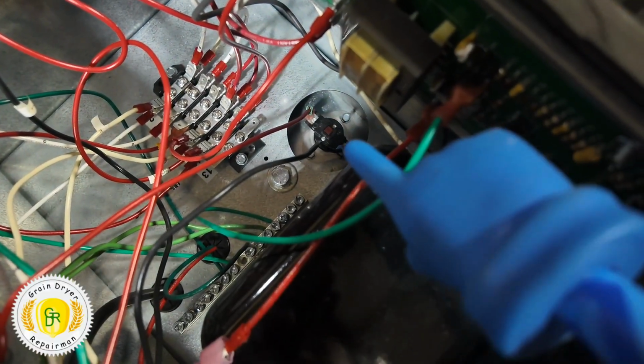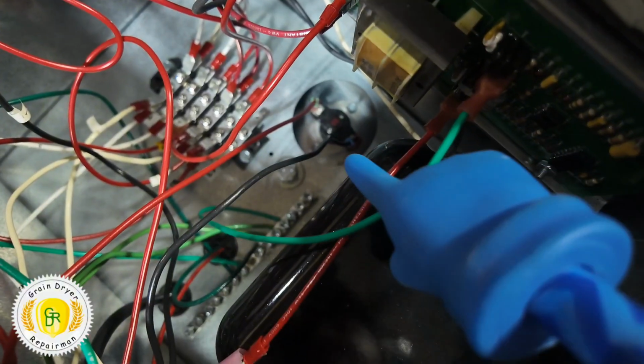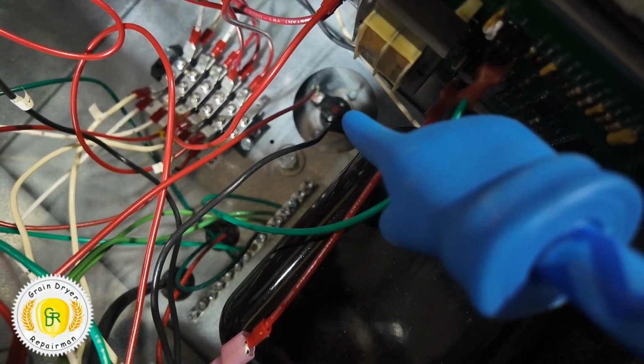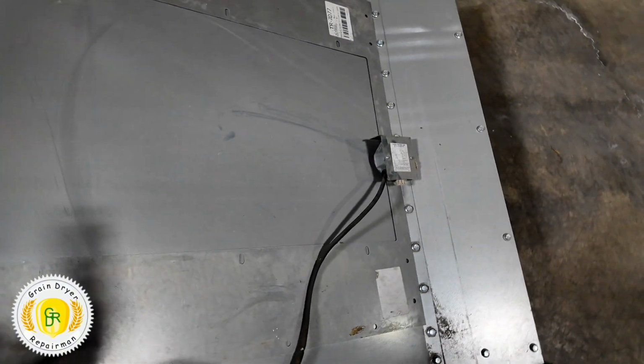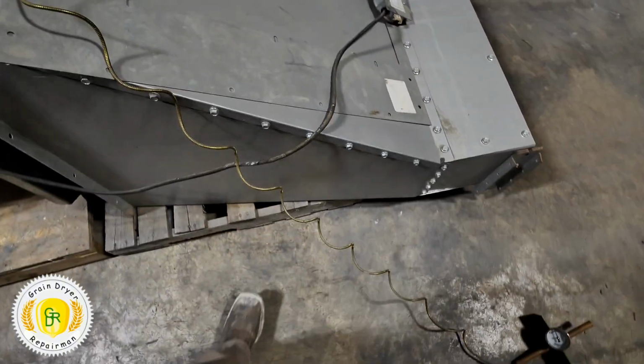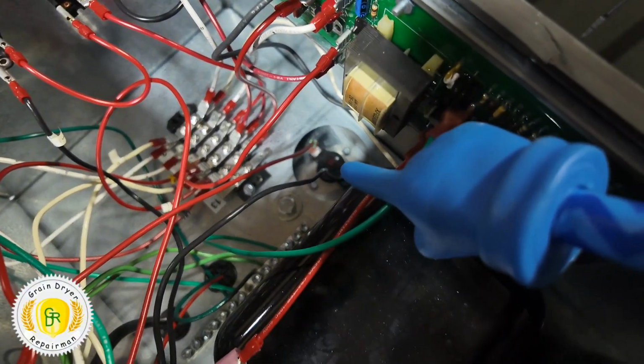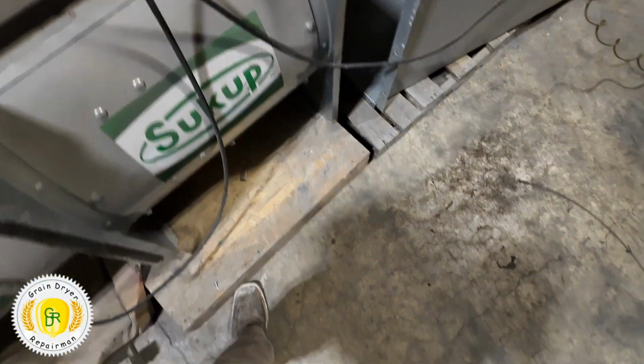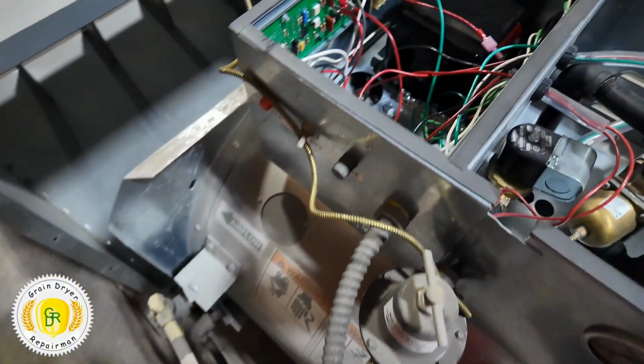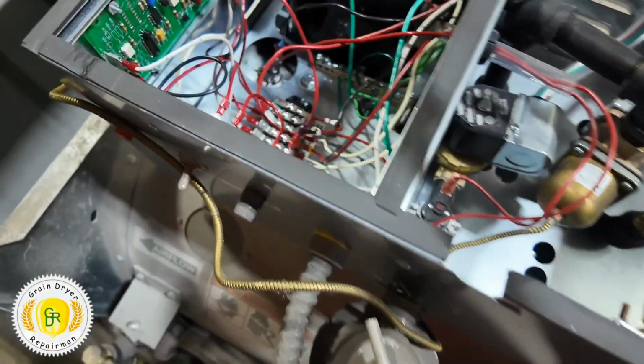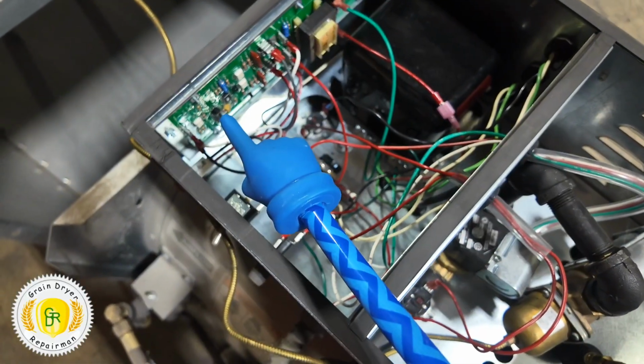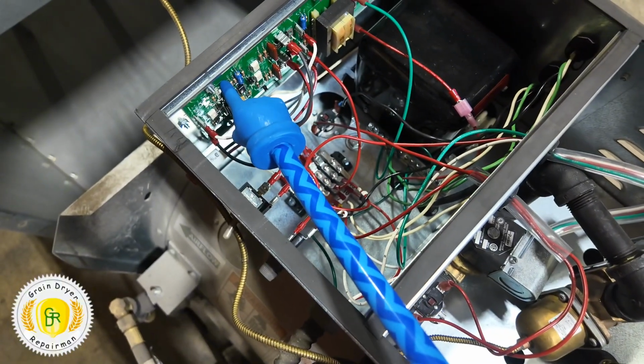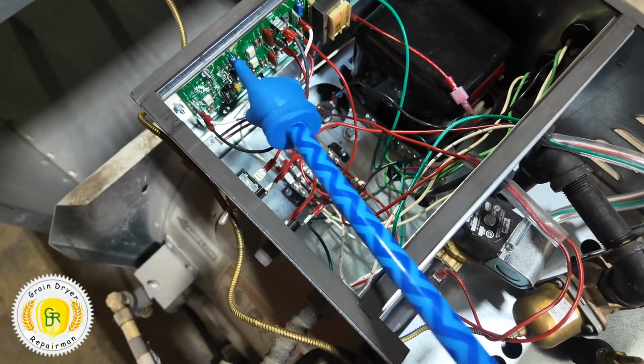Down in there, if your burner lights and your fan is not running, it will trip that housing over temp. If your vapor coil was to get a hole in it and start putting out big flames, this switch will trip. There is a safety in here, almost identical to the safety in the bottom of the burner box. If your burner lights but burns for about a minute and shuts off, it could be the flame sensor. This burner board controls your burner. The only thing that this burner board will shut the gas off for is if it is not sensing flame.